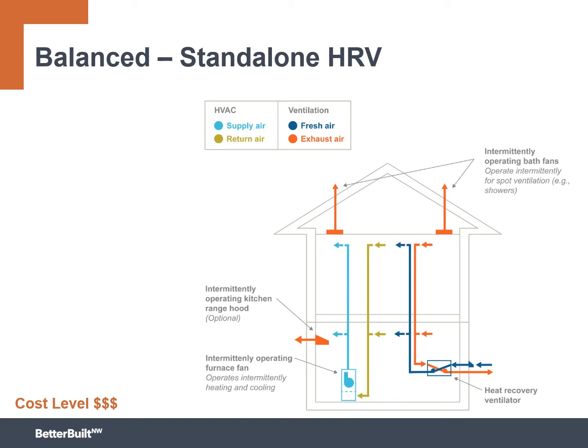One option with these is to exhaust out from the bathrooms. That's actually our preferred option. This often has very warm air, especially during shower and bath time, which can help treat the indoor air quality of the home by removing it, as well as potentially meaning that we could use a slightly smaller dedicated local exhaust fan in each bathroom to meet our International Mechanical Code requirements. We'll go into that in a little more detail down the road here. We also really like that the new air coming into the home can be delivered into as many rooms as you care to duct it to, reducing the risk of bad indoor air quality throughout the home.